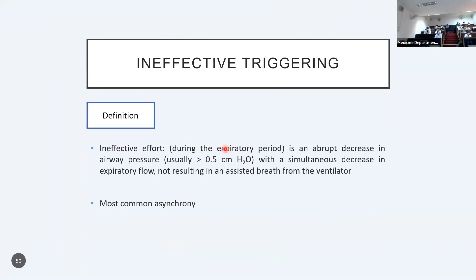So magnitude of flow is decreased. This is the most common asynchrony, and it can occur both during expiration and inspiration with a positive deflection in the flow scalar and with negative deflection in the pressure scalar. Important thing here is this scalar, which is known as esophageal pressure. Esophageal pressure scalar is usually measured by a nasogastric tube, which measures intraesophageal pressure. It reflects the intrapleural pressure, and a negative intrapleural pressure signifies a patient's trigger that he wants to take a breath.